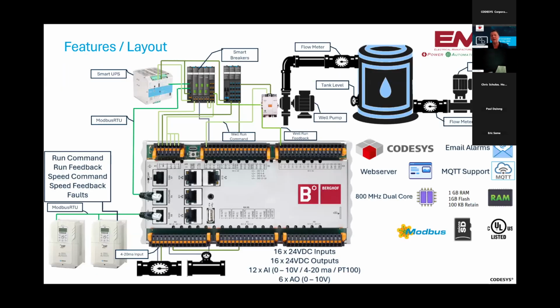So here's a look at our hardware. It's a little bit of an eye chart, but I think everybody here can hopefully understand what we're showing. In the upper right, you've got your booster pumps. You've got a tank that we're filling. You don't have to have a tank. You could be boosting pressure directly from the water treatment plant. It really doesn't matter. But for those booster pumps, we're able to control them over Modbus. We've got 3 different flavors right now, and it's a product feature we'll discuss a little bit, but we can control Danfoss, Yaskawa, and worldwide, up to 4 of those. And basically we're setting set points and maintaining pressure for the system.